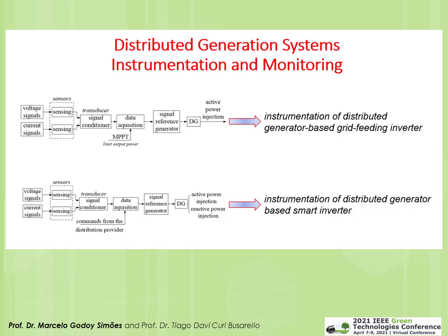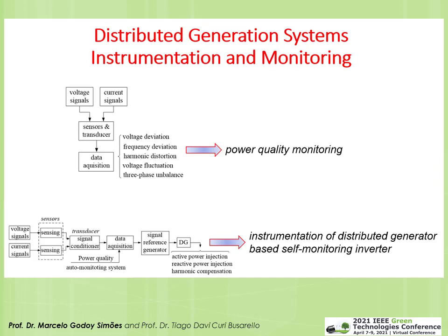In distributed generation systems, we need a lot of instrumentation and monitoring. Here we see the instrumentation of a DG-based grid-feeding inverter, where voltage and current signals are acquired by the system to perform maximum peak power tracking. The bottom of the figure shows instrumentation of a DG for a smart inverter, where we may have commands from the utility to enable active power injection or reactive power management.